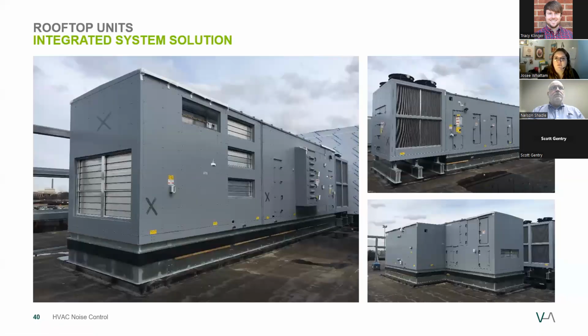So these are a few photos of an installed NCC VCR curb to show that there are no size restrictions in this single source noise control solution. And then you can check out this sample schedule that can be put directly into bid documents. It specifies a guaranteed NC level and a PE stamp to, again, take any noise control risks away from the designer.